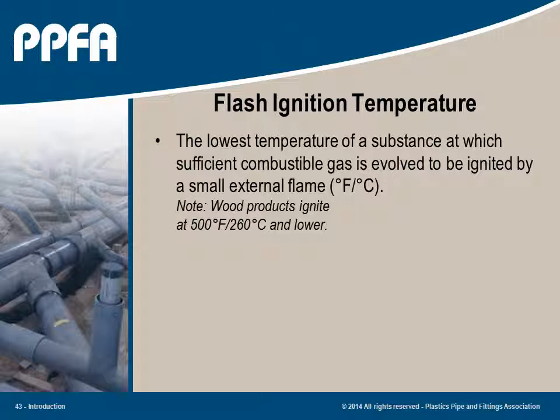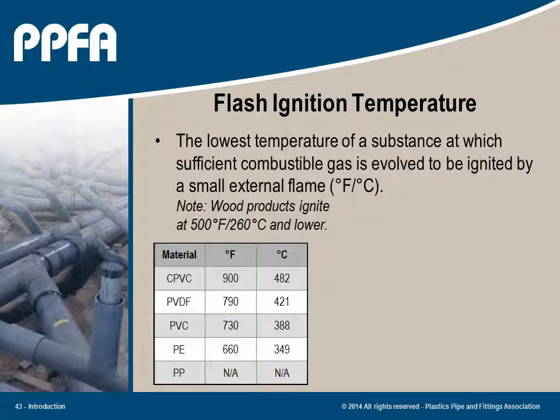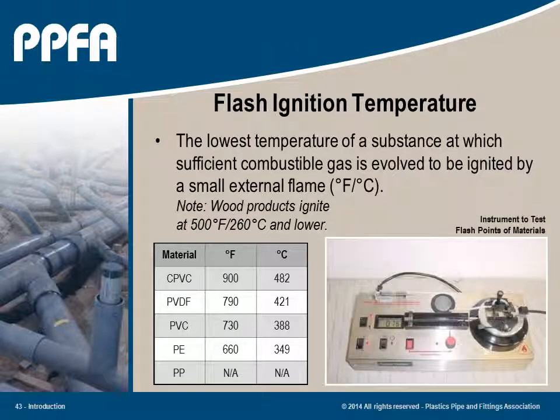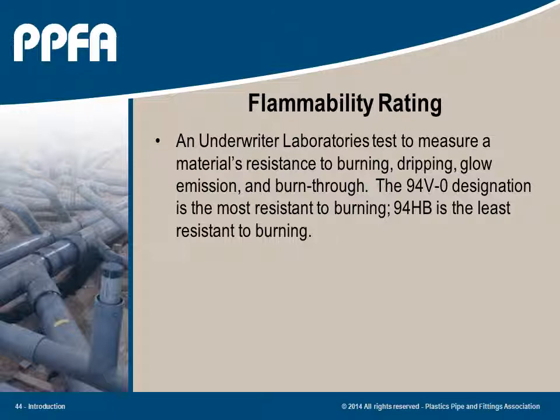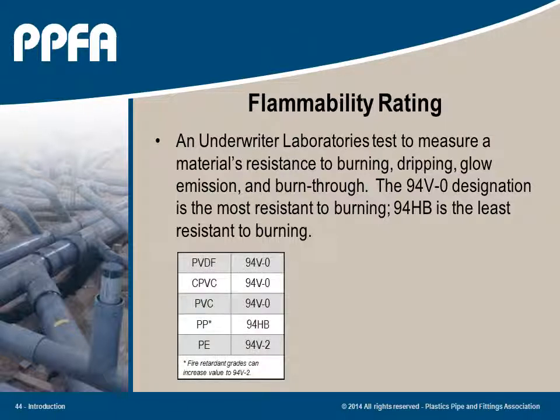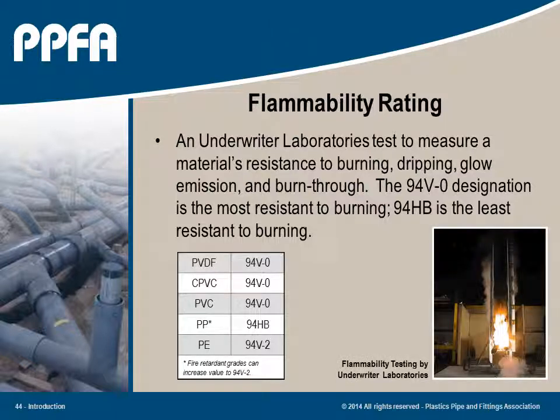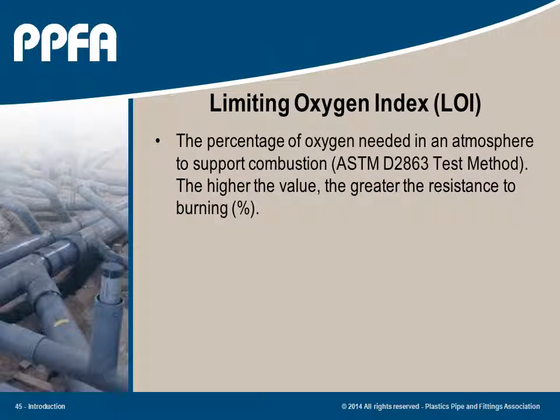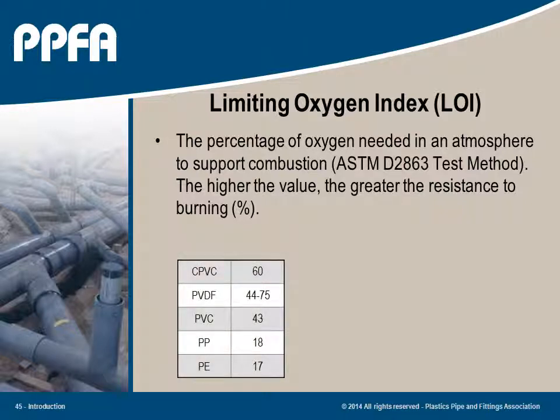Plastic ignition temperatures are 200 degrees Fahrenheit higher than wood products. In no case can plastic piping materials flash or self-ignite until temperatures approach 650 degrees Fahrenheit or higher. Vinyls and fluoropolymers will not support combustion. Polyolefins are less resistant to Underwriter Laboratory and other agencies' flammability testing. The limiting oxygen index, LOI, is another method of determining which materials burn easier than other materials. For example, cotton requires an LOI of 16, while CPVC and PVDF have an LOI of 44 to 75.